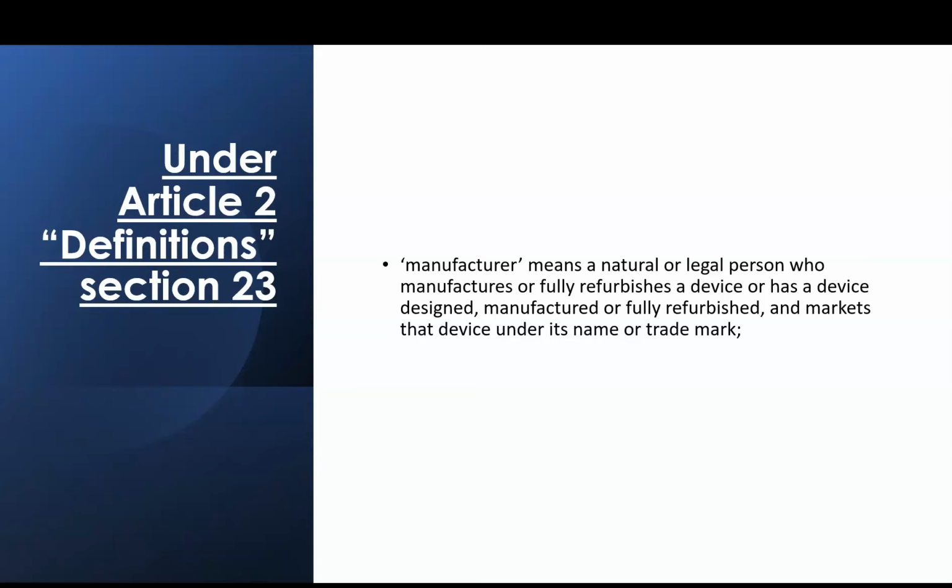The manufacturer designs and manufactures the in vitro diagnostic medical device with the intent of selling it in the European marketplace. In vitro diagnostic medical device equipment can be refurbished and sold again onto the European market.